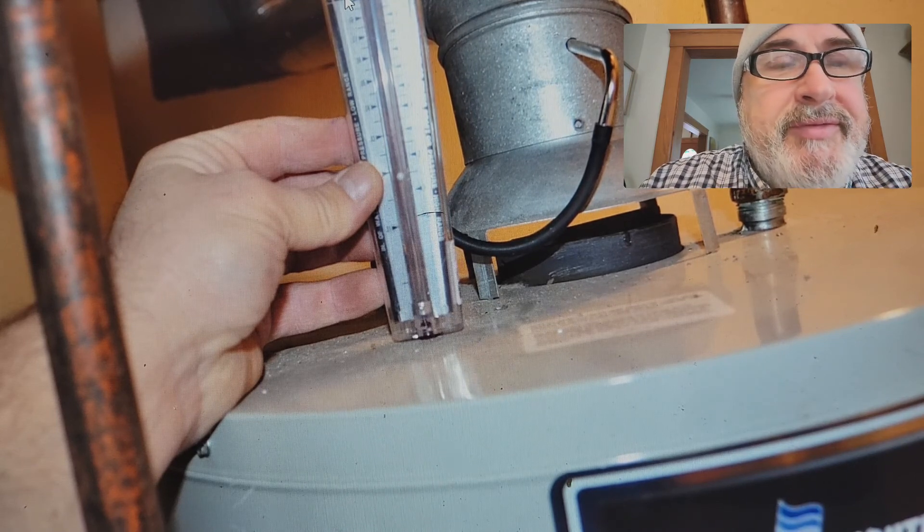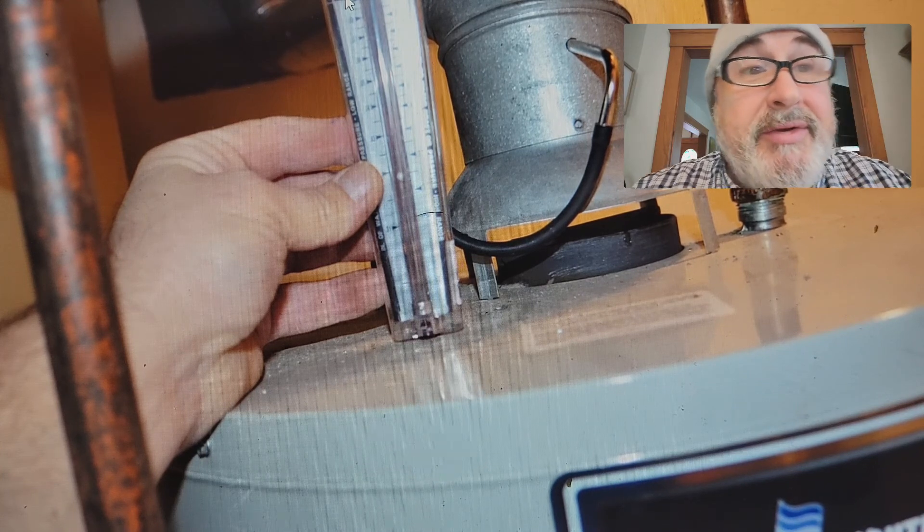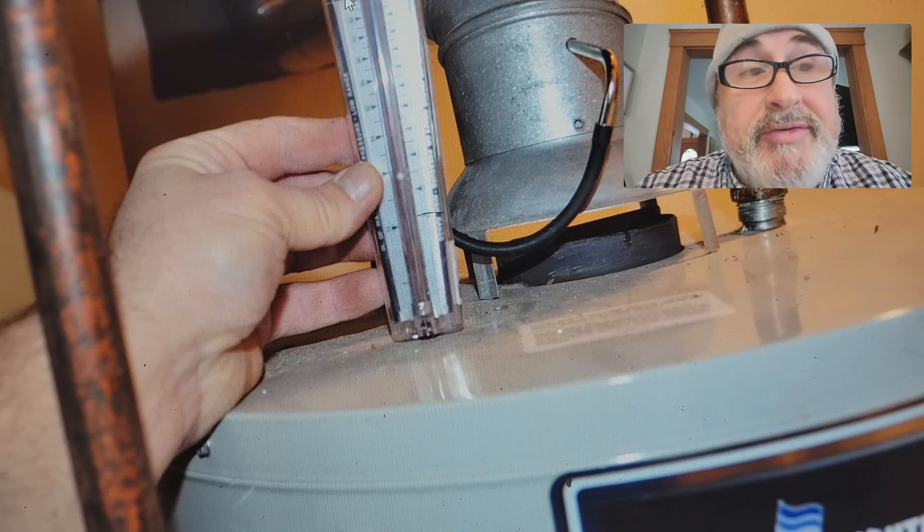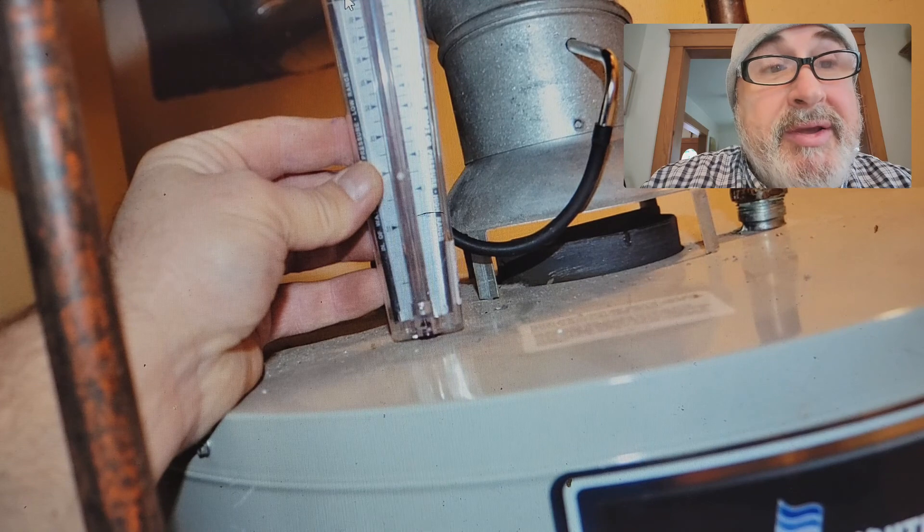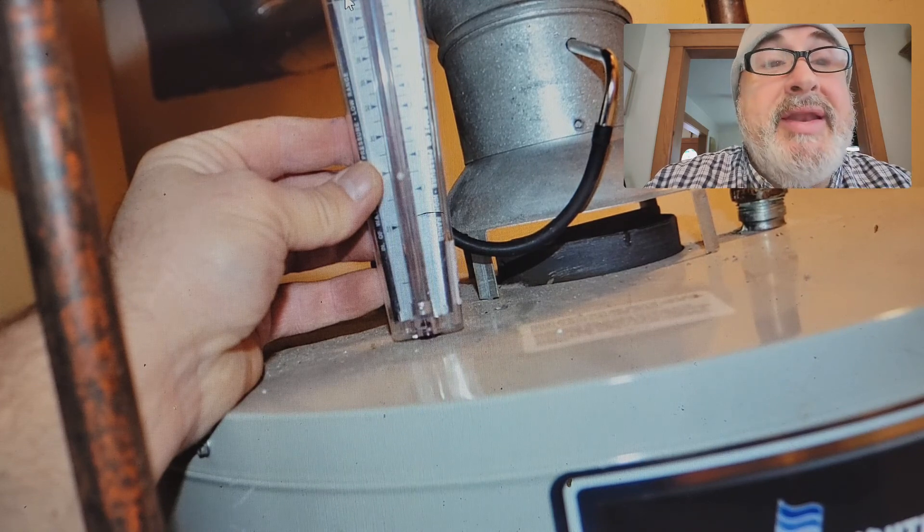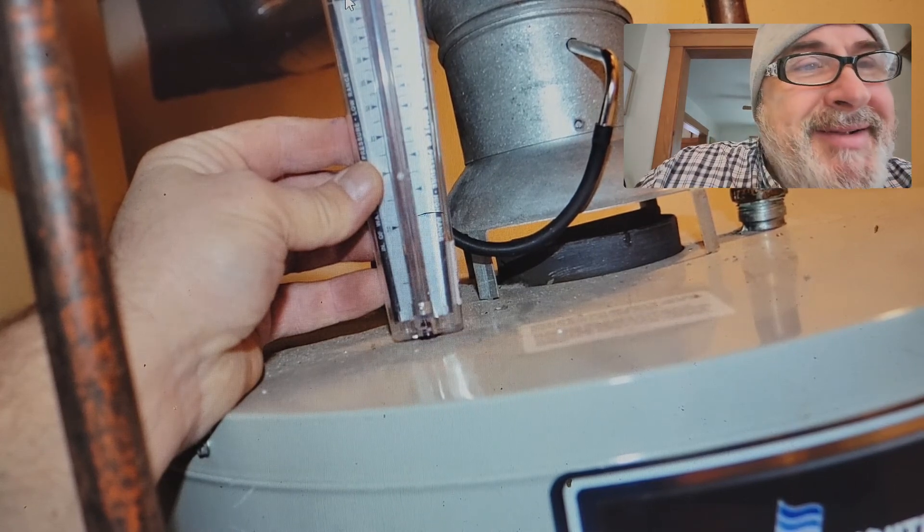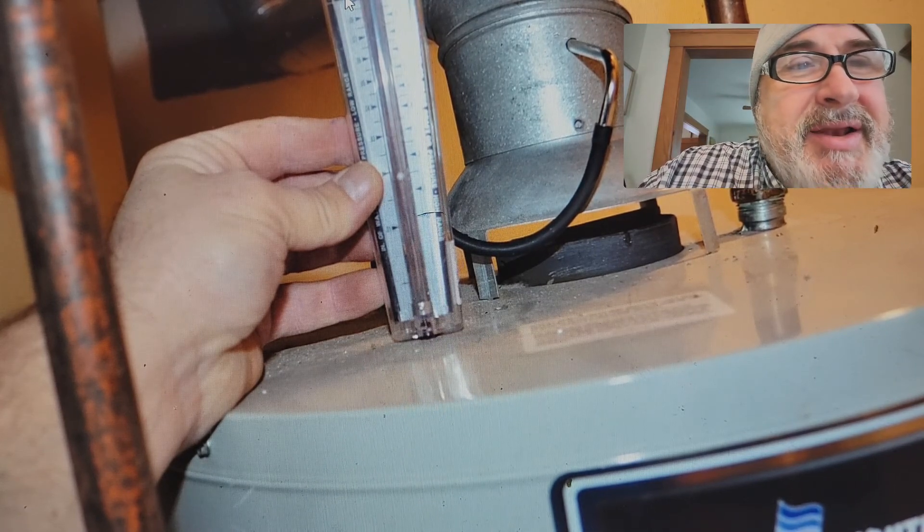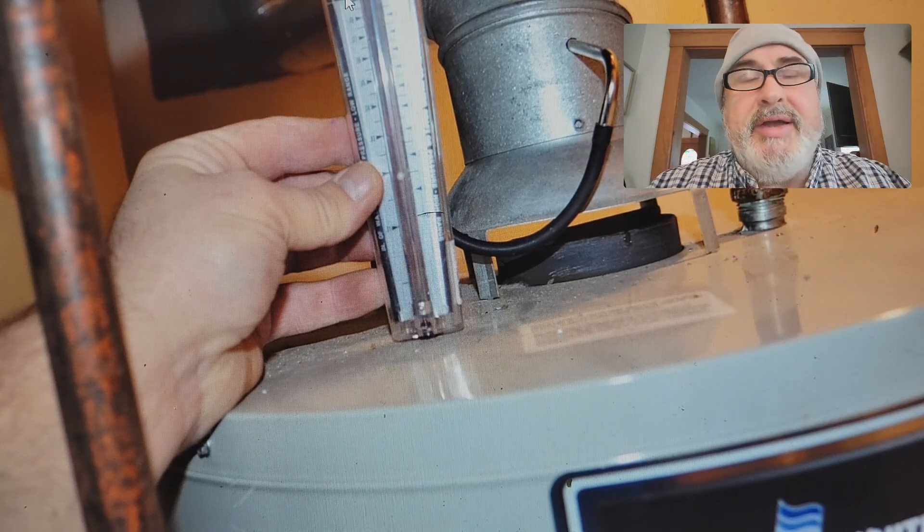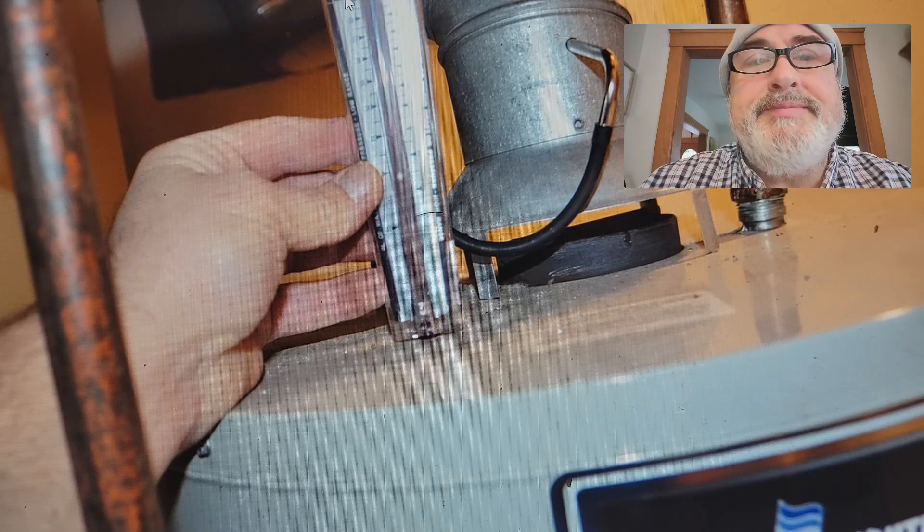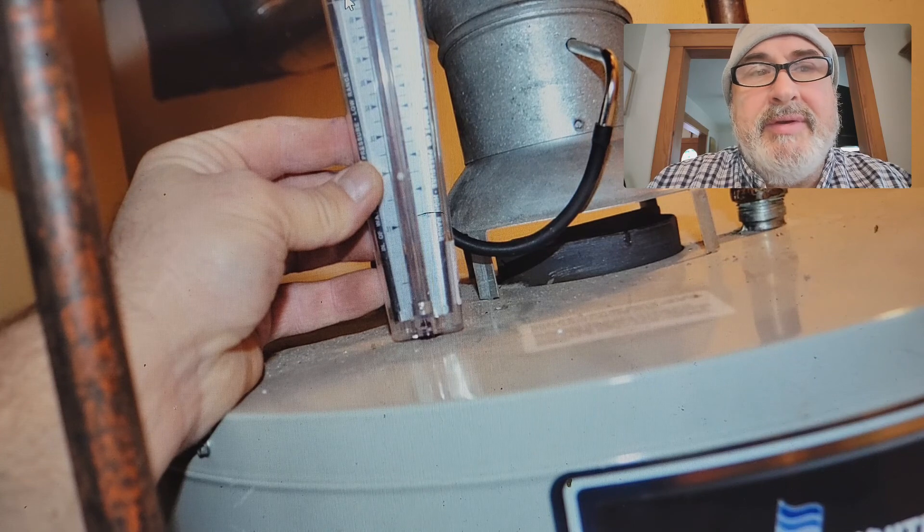So if the burners, and this is draft not just on your water heater, but draft on your gas appliances, your furnaces. And so if you have poor draft, you can create incomplete combustion. And incomplete combustion means that now you don't have enough oxygen going down below where the water heater burners are at. And now you're burning carbon dioxide or you just don't have enough oxygen supply and you create carbon monoxide and aldehydes. And so basically poor draft is a key element. You always got to make sure.